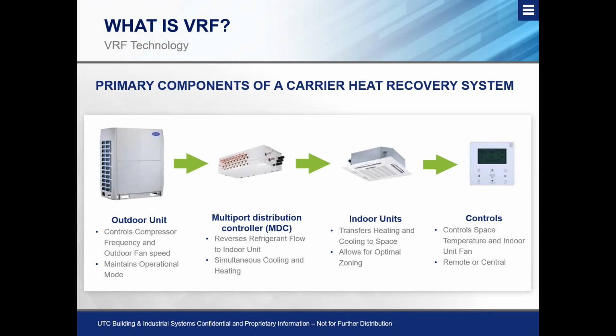Now, the only difference between this system and a Toshiba Carrier system that I talked about before is that this outdoor unit has two pipes. So this is a two-pipe heat recovery. The difference between a Carrier and a Toshiba Carrier system is that the Carrier system has two pipes that leave the outdoor unit. That separation process into three states of refrigerant happens in the MDC on the Carrier system by use of a gas liquid separator to create hot gas, liquid, and suction. Obviously, your three states of refrigerant. That process on the Toshiba Carrier system happens in that outdoor unit by opening up a solenoid valve to bypass the condensing coil and send hot gas directly on the hot gas line to our flow selectors.